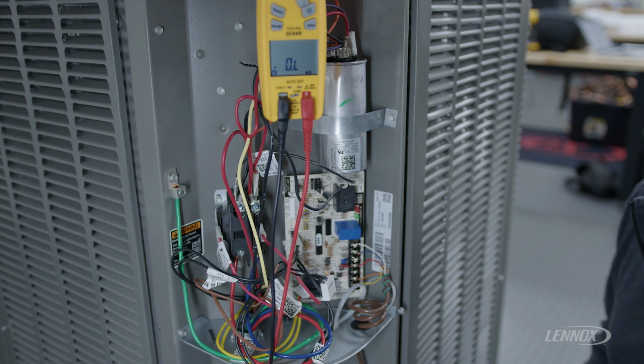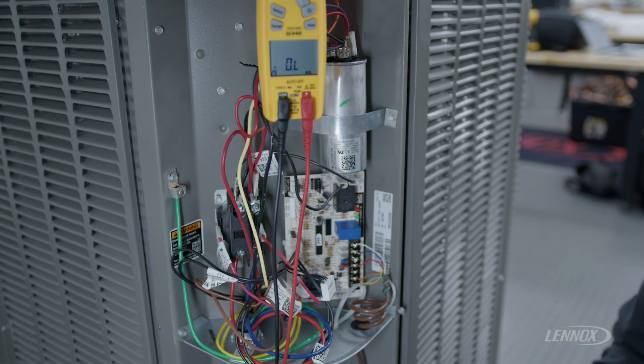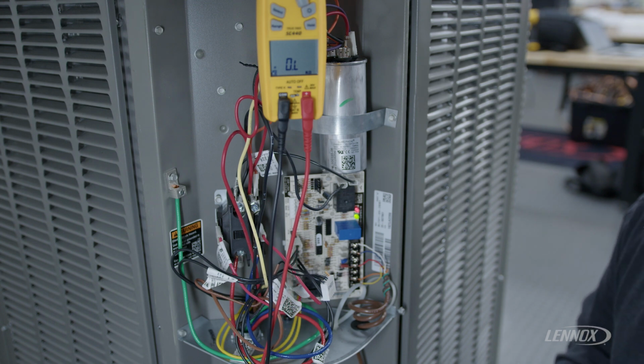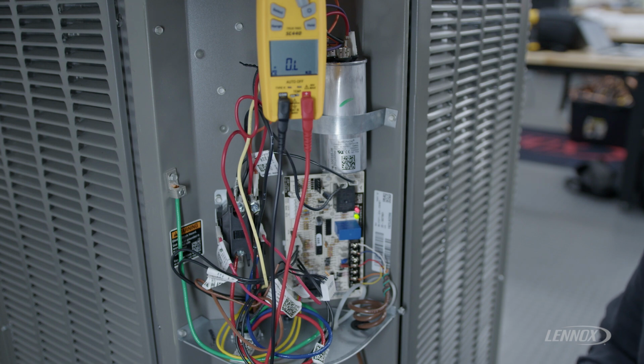The next error code or state you might see on our defrost control is a simultaneous fast flash, a half-second pulse designating a fault state. This simultaneous fast flash tells us there's a fault with the ambient temperature sensor, which is an integral part of this heat pump that helps it understand and process the defrost cycle.